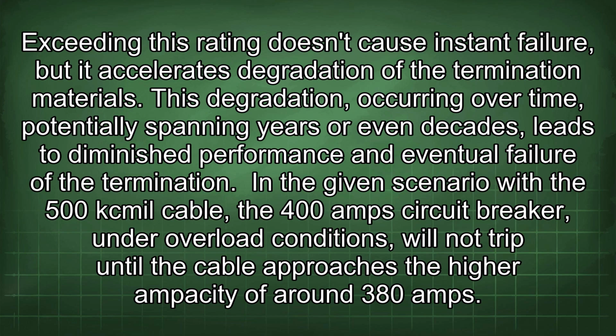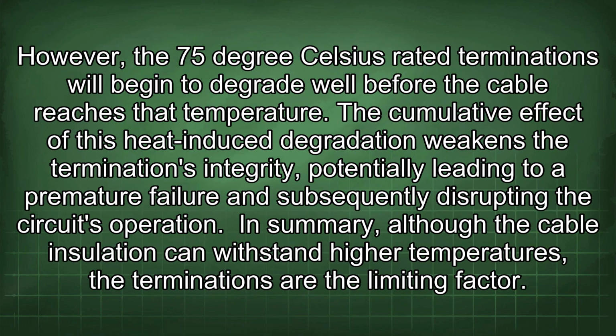termination. In the given scenario, with the 500 kcmil cable, the 400 amp circuit breaker, under overload conditions, will not trip until the cable approaches the higher ampacity of around 380 amps. However, the 75 degrees Celsius rated terminations will begin to degrade well before the cable reaches that temperature. The cumulative effect of this heat-induced degradation weakens the termination's integrity, potentially leading to a premature failure and subsequently disrupting the circuit's operation. In summary, although the cable insulation can withstand higher temperatures, the terminations are the limiting factor.